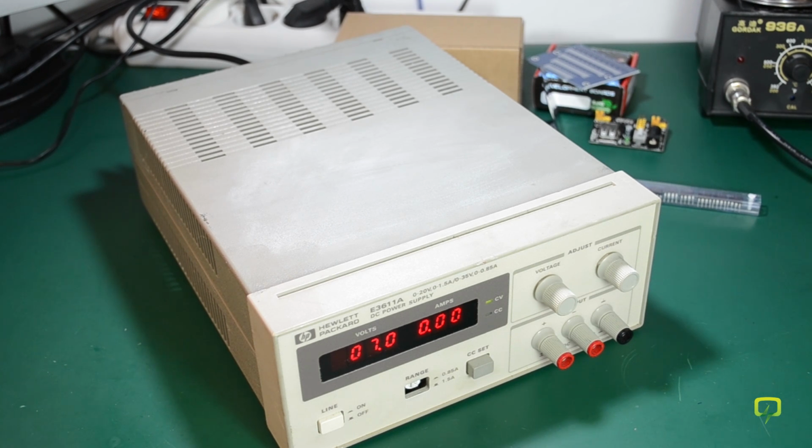So there won't be any repair video on this power supply, but what I can do is do a teardown, calibrate the display and clean the power supply. I have looked up the calibration procedure and found it in the service manual. At first glance it should be quite simple to do, but all that will be in a future video. These were all the mail items for today.